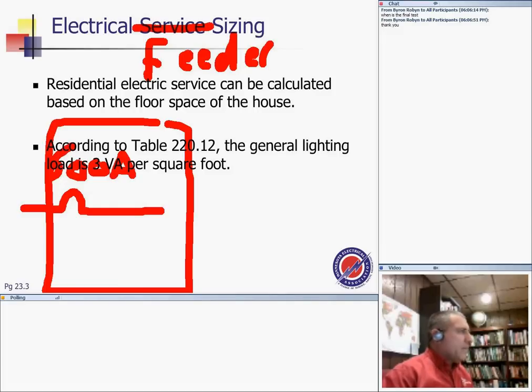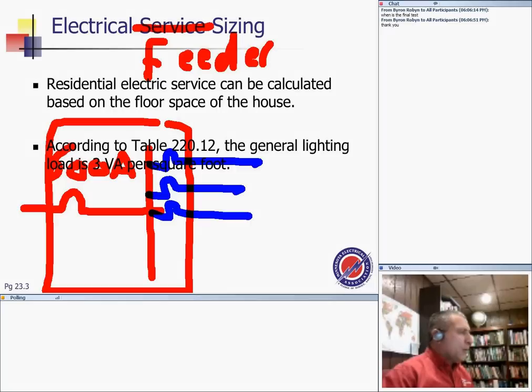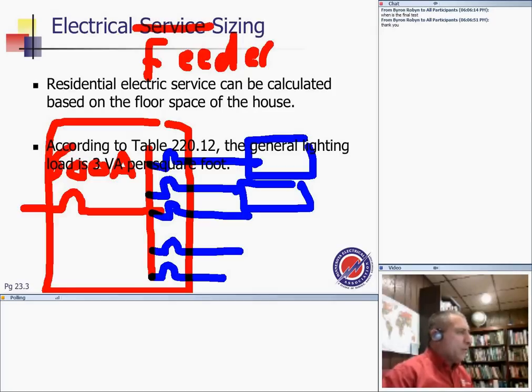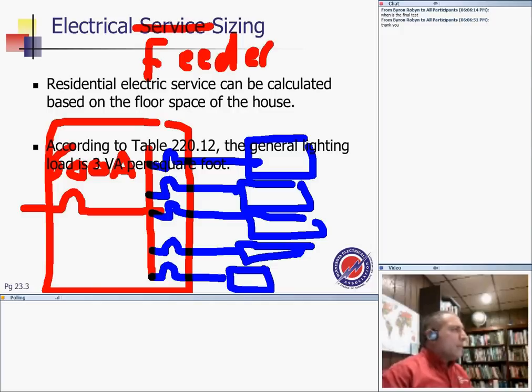For my service panel, I'm going to install a bunch of circuits, different apartments in this apartment building. So my panel apartment 1, here's panel apartment 2 and panel apartment 3, and as you can tell it's 4, and as you can tell it's 5. So which one is feeder and which one is branch circuit? Which one is service? That cable coming to your building, that's going to be, my friend, your service.